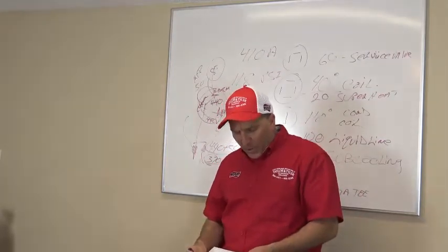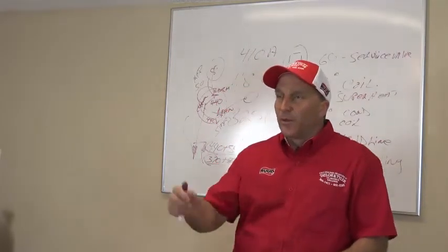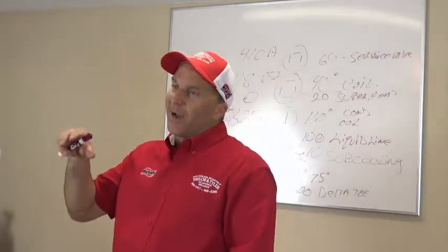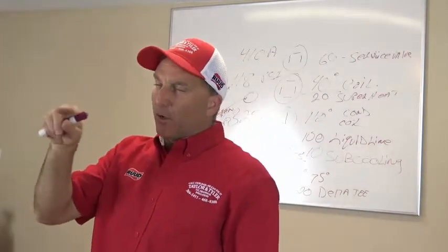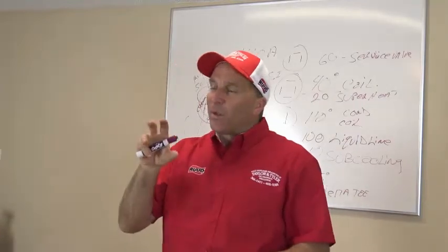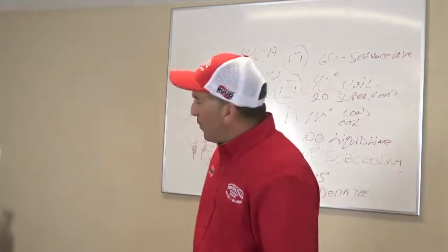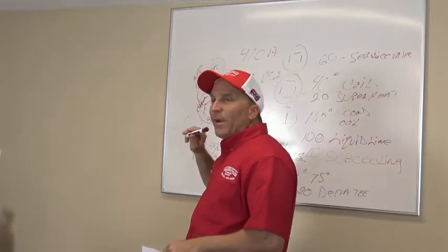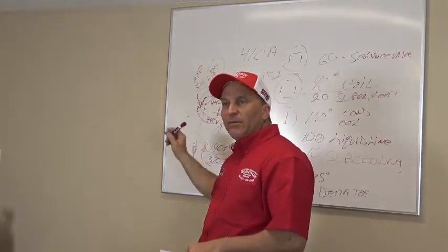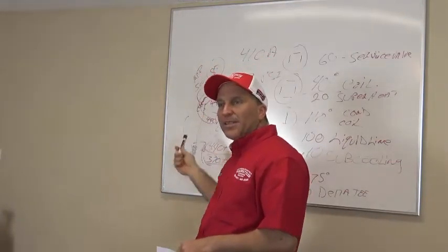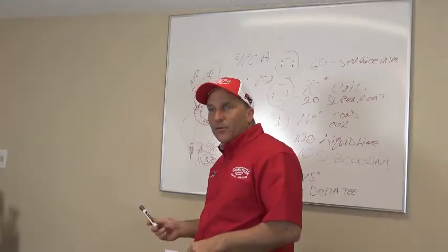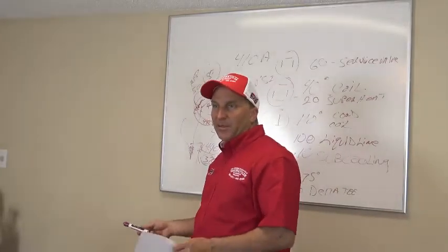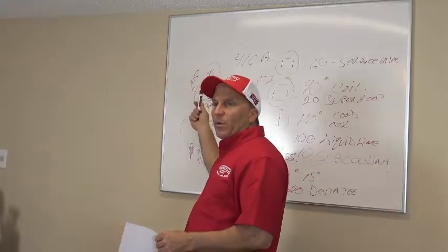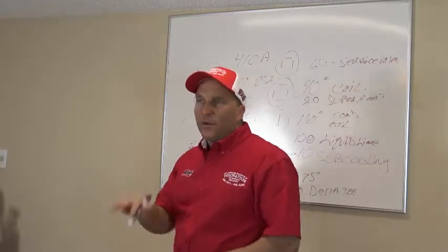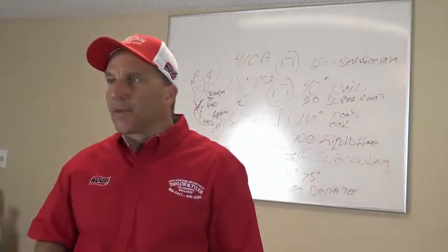Okay. So when you read a capacitor, you put your microfarad tester on it. So you have a meter that has MFD on it, or UF. That's going to tell you what microfarads you're reading. So if you put your meter on here and it's reading 42 microfarads and it's supposed to be reading 50, you have a weak capacitor. Then you replace that capacitor. If it's reading 28, you replace it. If it's reading 48, I wouldn't replace it. It's only 2 off. You can stay within 10%. Okay?